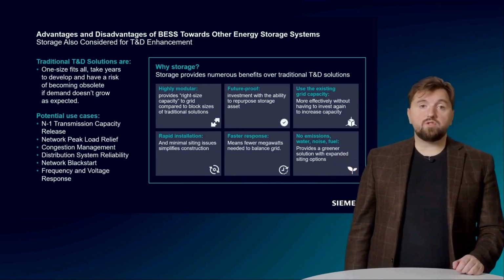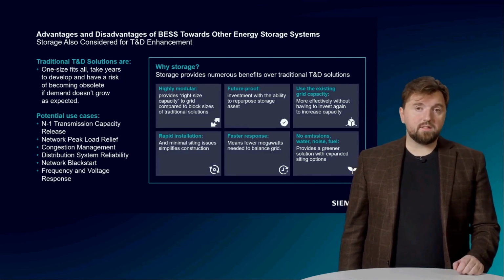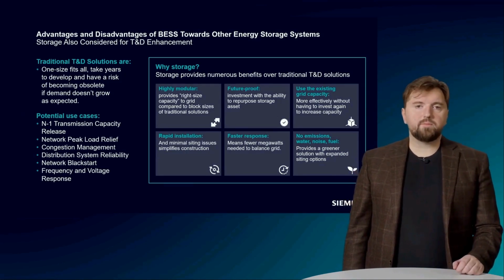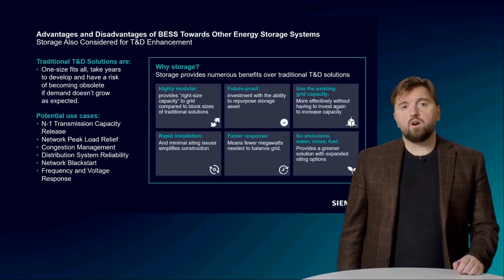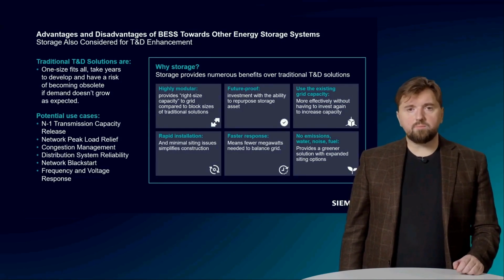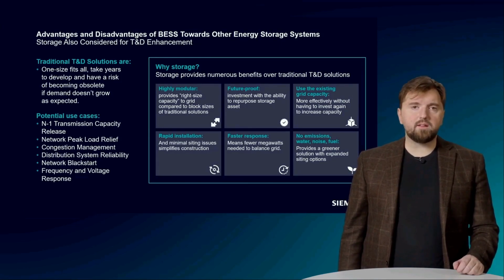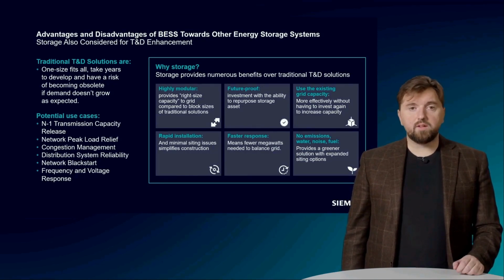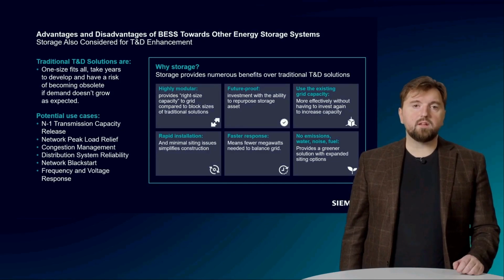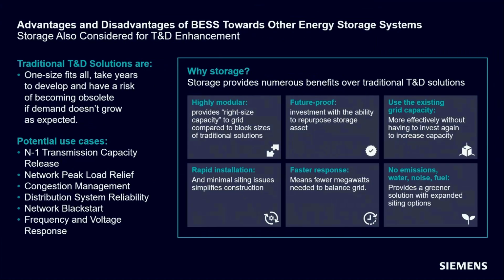When it comes to advantages of BESS in comparison to conventional T&D solutions, these are numerous. Conventional solutions often follow a one-size-fits-all approach and can become obsolete if demand doesn't develop as expected. On the other hand, BESS offers high modularity with a right-size capacity for the grid, compared to the block sizes of traditional solutions. Due to its versatility, its usage can be adapted to the actual system needs. It can also maximally exploit existing grid capacity as a non-wire alternative.